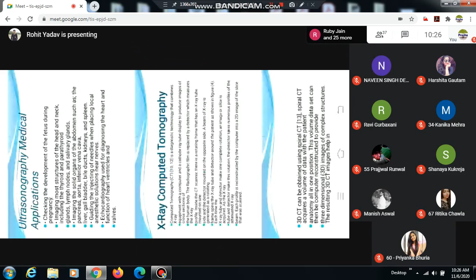Start with CT scan, X-ray computed tomography. Computed tomography is a diagnostic technology that combines X-ray equipment with a computer and a cathode ray tube display to produce images of cross-sections of the human body. The radiographic film is replaced by a detector which measures the X-ray profile. Inside the CT scanner, there is a rotating frame that has an X-ray tube mounted on one side and a detector mounted on the opposite side. A beam of X-ray is generated as the rotating frame spins the X-ray tube and detector around the patient as shown in the figure.